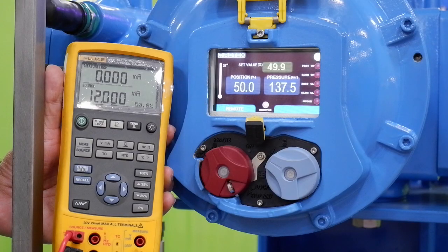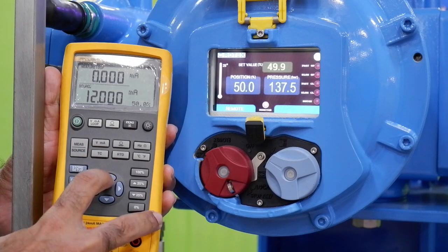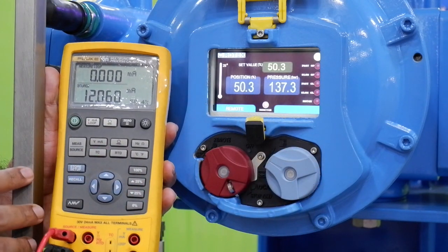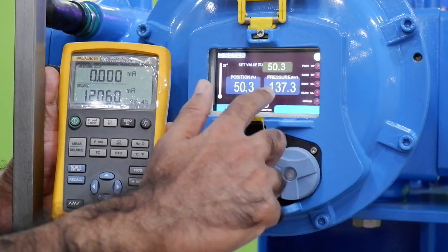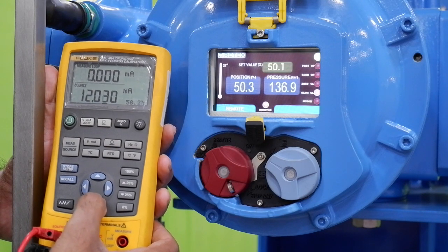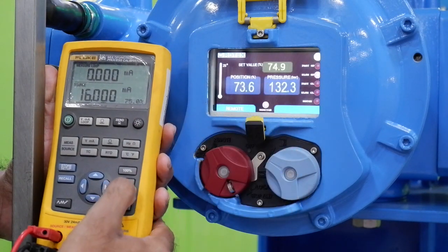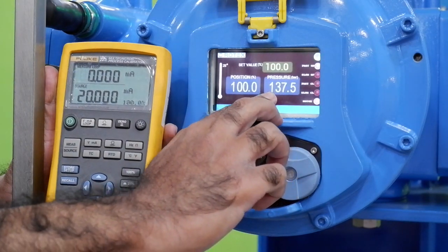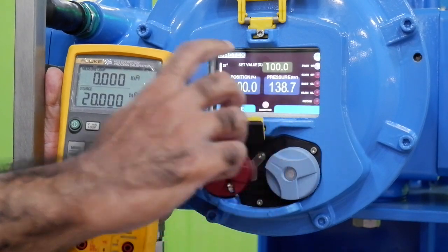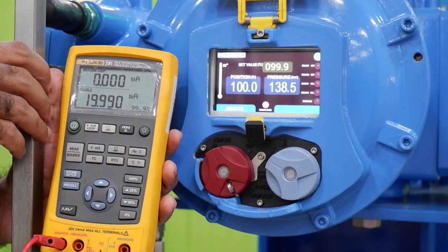Here we will see how the motor is turned on in this actuator. For small changes in the input, the motor is off as shown in the indication, and the motor never turns on until the pressure falls below accumulator min, which is already set. Now if I make a major change in the input, the motor starts as soon as it has gone below 125 bar, which is the setting for the accumulator min. So the motor maintains a pressure between the accumulator min and max values, but that happens if there is a major change in the input depending on the accumulator size.